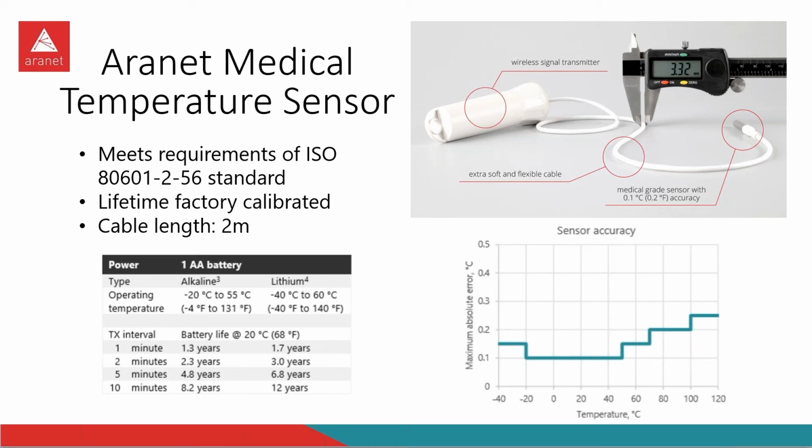It is lifetime factory calibrated, so the temperature sensor does not need to be recalibrated. It has medical grade precision, meaning in this temperature range where you would operate with this system, it has a 0.1 degree accuracy. Normally, human body temperature is measured from 30 to plus 40 degrees Celsius. Therefore, within this range, we have a 0.1 degree accuracy.